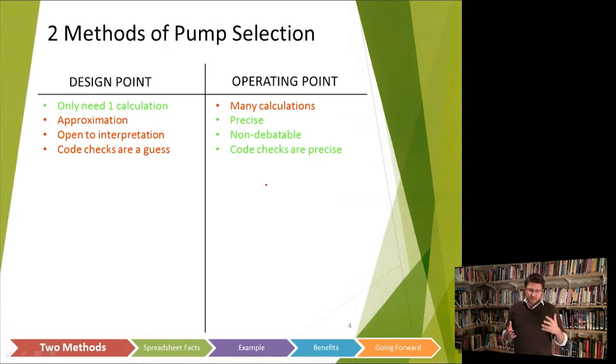However, the design point method is an approximation, whereas the operating point method is precise. You actually find out where the pump will be operating. The design point method is open to interpretation. Some people could say, well, it's close to the curve, it's far from the curve. You know, who's to say which is close and what's far?